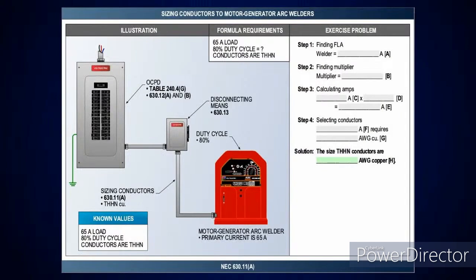You got a motor generator. We got a 65 amp load and 80% duty cycle. So step 1, 65 amps. Step 2, look at table 630.11, get the 80% there, come across, find out what the multiplier is, calculate it, and size your conductor. Okay.